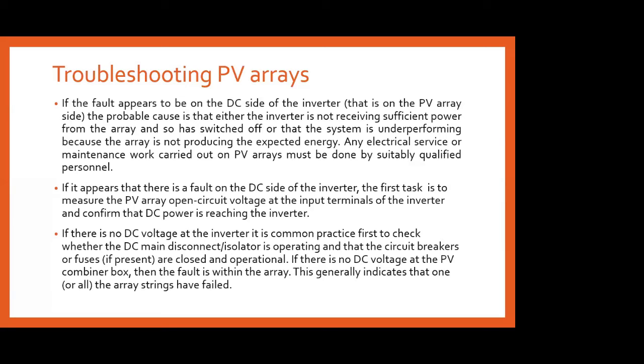Then, if it appears that there is a fault on the DC side of the inverter, what is the first task we have to make? The first task is to measure the PV array open circuit voltage at the input terminals of the inverter, and to confirm that the DC power is reaching the inverter. And of course, if there is no DC voltage at the inverter, what we have to do first is check whether the DC main, that is the isolator, is operating. If that particular isolator is not operating properly, you have to check with the fuses also, if fuses are present, whether they are closed and operational. If there is no DC voltage at the PV combiner box, then the fault is within the array itself. If everything is fine, if the isolator is working fine and the fuses are working fine, then the problem will be with the array itself.